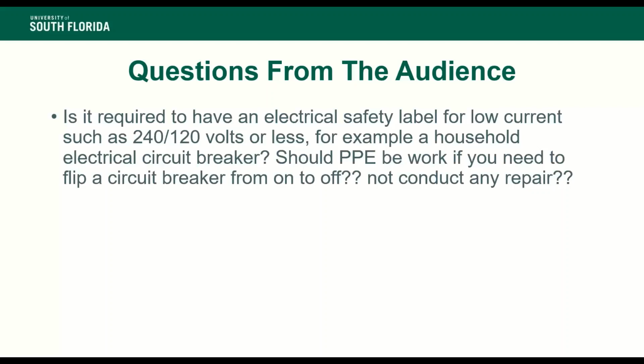Our next question. Is it required to have an electrical safety label for low voltage, such as 240 or 120 volts or less, for example a household electrical circuit breaker? Also, should PPE be worn if you need to flip a circuit breaker from on to off, not conducting any repairs? I'll go ahead and take that one as well. The arc flash issues do not apply to dwellings. You do not have to have all of the PPE protection for dwellings. They really come into play in an industrial setting and industrial grade equipment. The standard explicitly says it does not apply to panels within dwellings.